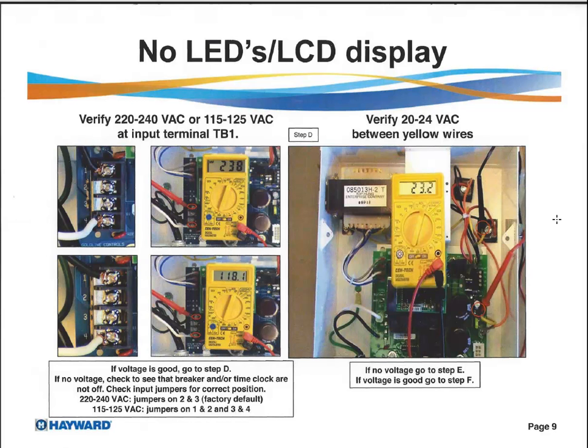So we got our proper voltage. Now we want to verify that we've got 20 to 24 volts between the yellow wires. You've got a yellow wire here and a yellow wire here. You should have somewhere in the neighborhood of 24 volts. You can read the rest, but this is starting troubleshooting 101. If it is a brand new install, go straight to this. If you have it wired 110 and it's preset at 240, it will come up dimly lit, possibly for a few seconds, and then it'll go blank. So you need to know what you are wired for and what your voltage is.